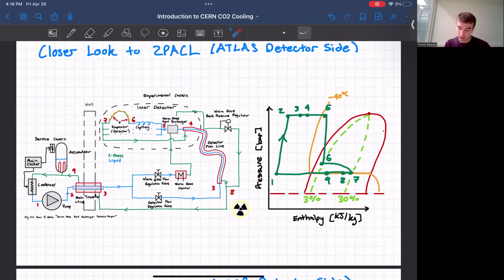So with the warm nose heat exchanger, we are entering the evaporator at around 3% vapor quality and exiting the evaporator at around 30% vapor quality. This is because we want to avoid boiling the CO2 to higher vapor qualities. Because if we boil too much and we reach gas, the heat transfer coefficient is very poor and the silicon sensors will break. So our safety is 30% vapor quality at the outlet of the evaporator.